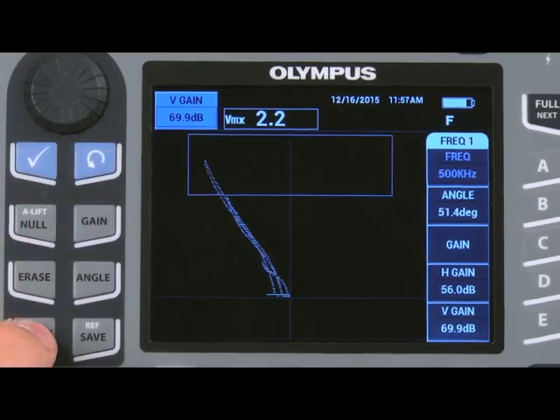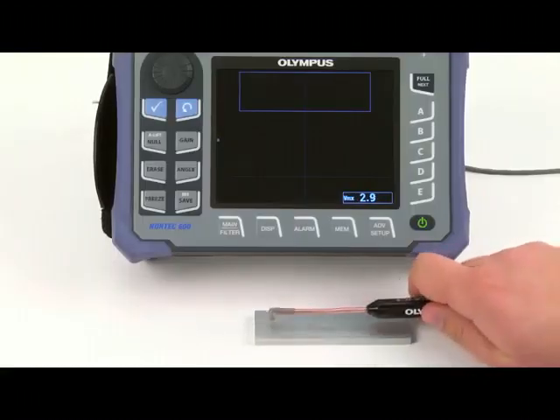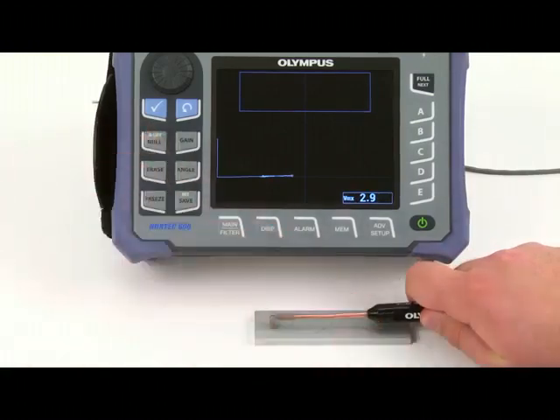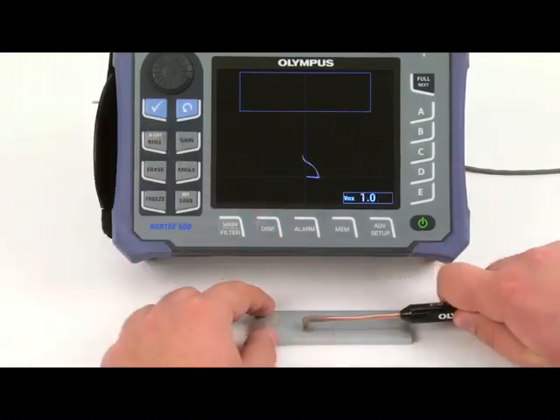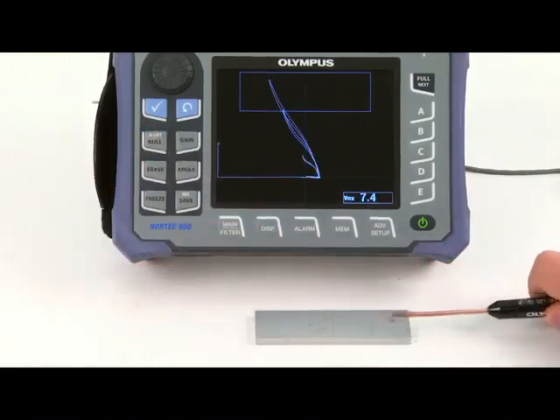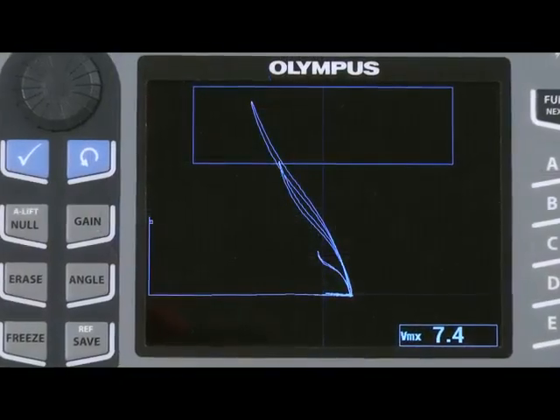Once completed, press freeze. Press full next to enter full screen mode. Place the probe on a defect-free area and press null. Rescan the standard. The newly acquired scan is now calibrated.